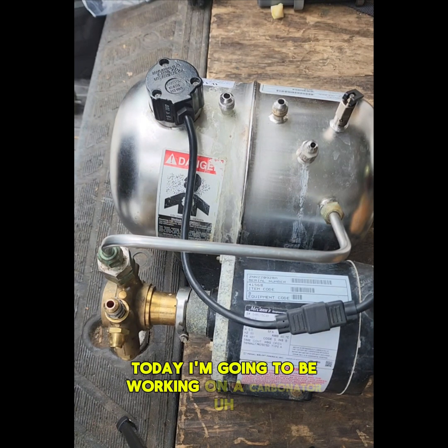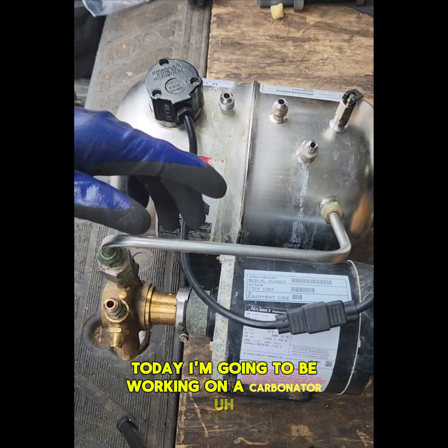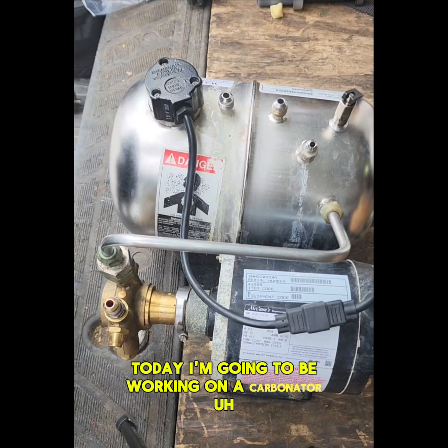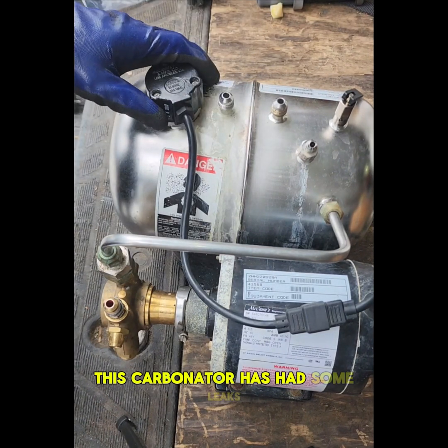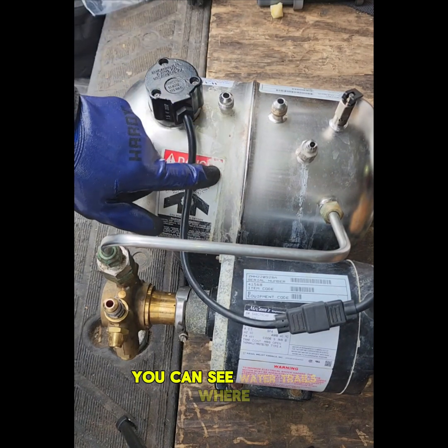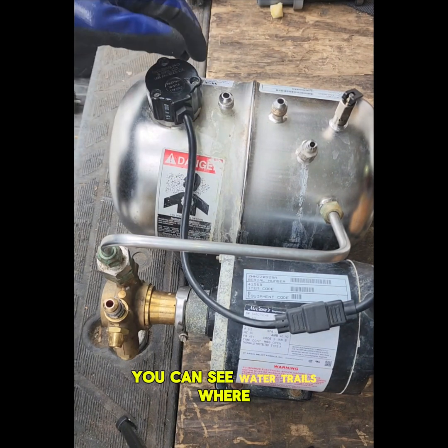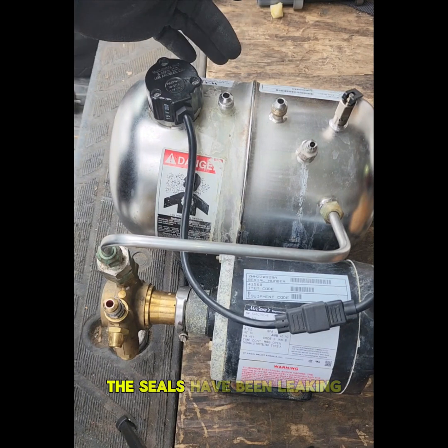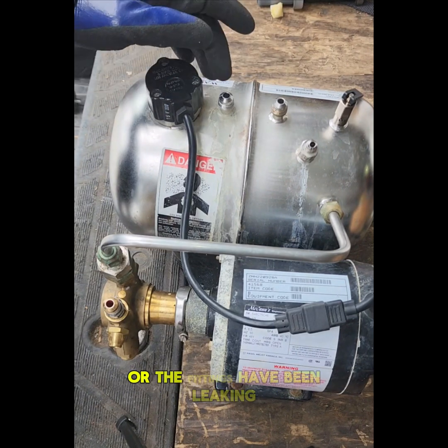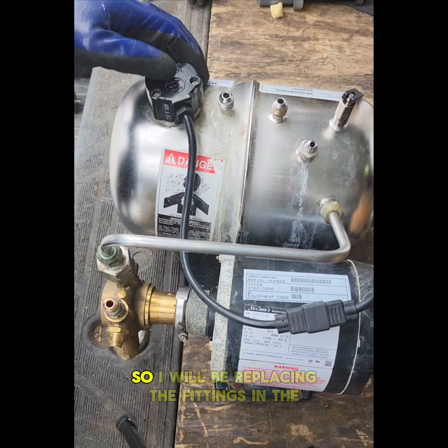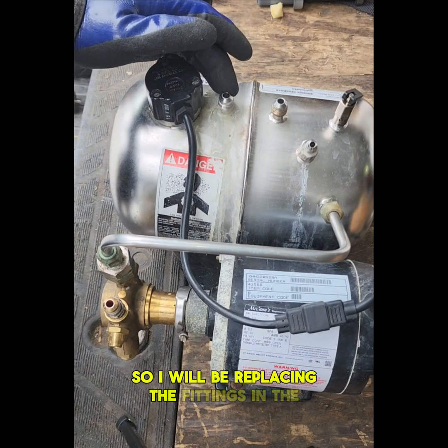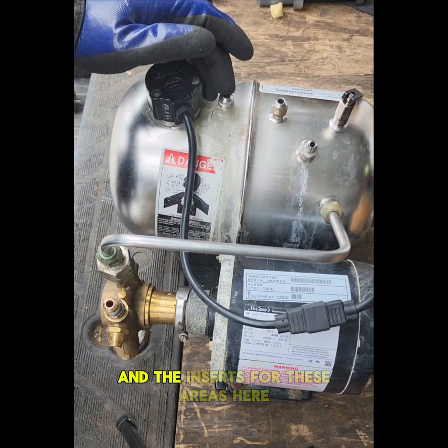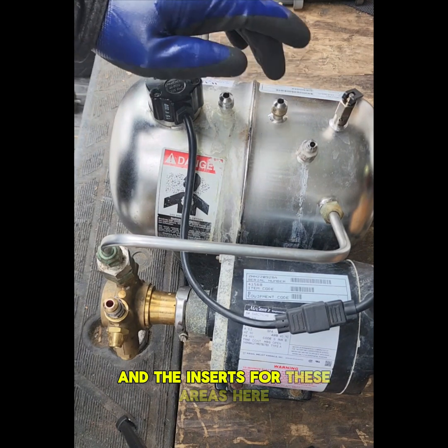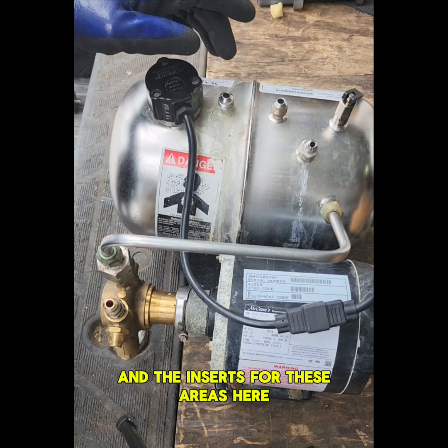Today I'm going to be working on a carbonator. This carbonator has had some leaks. You can see water trails where the seals have been leaking or the fittings have been leaking. So I will be replacing the fittings and the inserts for these areas.